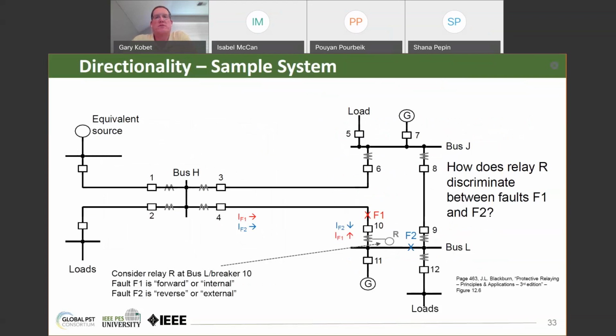So this is just a sample system to illustrate the point. If you look at bus L, which is in the lower right-hand corner, and breaker 10, which is on the line from bus L to bus H, the relay there just below breaker 10, and the boxes there, this is a single line representation of a 3-phase system. The boxes are circuit breakers. The breaker 10 on line 4, and then we have 2 fault locations, one fault F1 and one F2.